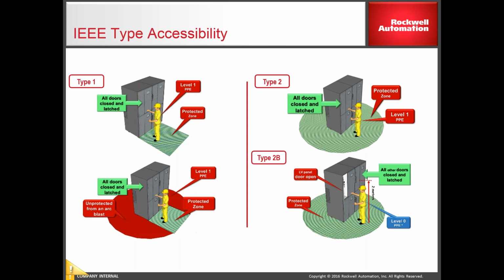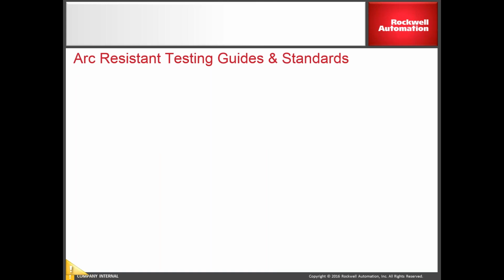And then there's Type 2B. What the B stands for is there's a low voltage section that's on the drive. If that door is open, you still have protection from an arc blast that might happen. So you've got total protection all around the equipment. That's what Type 2B accessibility means. The rest of the doors have to be closed, but that low voltage door can be open.